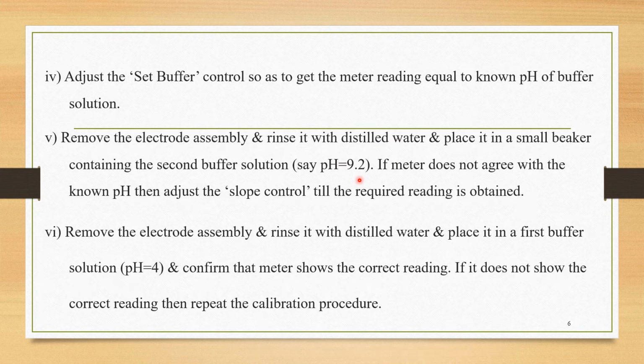If the meter does not agree with the known pH, then adjust the slope control till the required reading is obtained. So when we insert the electrode assembly into the buffer solution of pH equal to 9.2, if the meter reading is not equal to 9.2, then we have to adjust the slope control till we get the reading equal to, or near about, 9.2. The next step is to remove the electrode assembly, rinse it with distilled water, and place it in the first buffer solution, pH equal to 4, and confirm that the meter shows the correct reading.